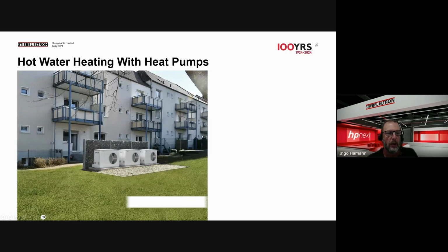For bigger setups, we can build so-called cascades - the industry knows cascades very well. Instead of having one big heat pump which will always start with the maximum it can do - if your whole house needs, at the coldest part of the year at 5 degrees outside temperature, 50 kilowatts, a 50 kilowatt heat pump will always start with 50 kilowatts and then stop - some people in the industry build cascades instead. So you have a smaller one starting first, and if it needs more power, the second one comes in, and then the third one comes in.